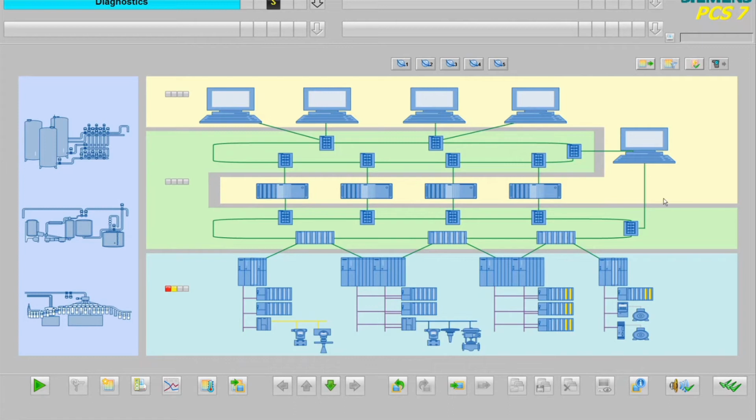If you're using intelligent Ethernet switches, so the Scalance range from Siemens is an example, then you can bring those into this layer, and the web browsers that you have on those, you'll be able to access from maintenance station, and you'll also get the alarms for them, so you can disable Ethernet ports and stuff from here. And if you've got a ring redundancy, that's fine. If somebody breaks the cable, it will carry on working, but again, you'll get an indication on here that something's wrong. That's important.